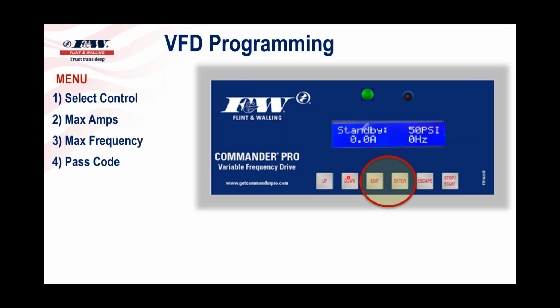Use your up and down button, select the second digit, hit enter. You do that 5 times, and once you hit enter, now you've got it password protected. So now, if you come back to the drive, you hit the edit and enter button before you go anywhere. It's going to ask you for that password.